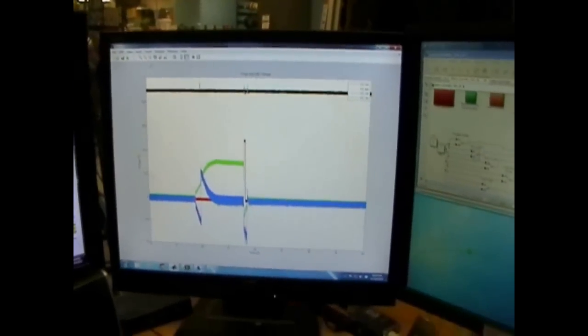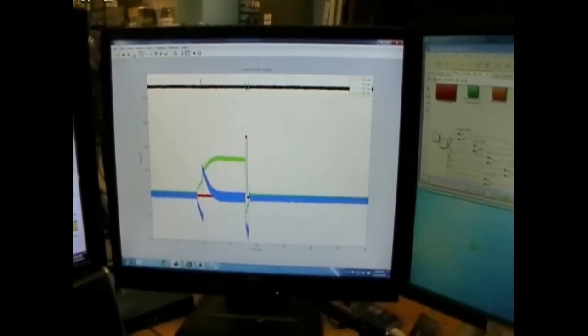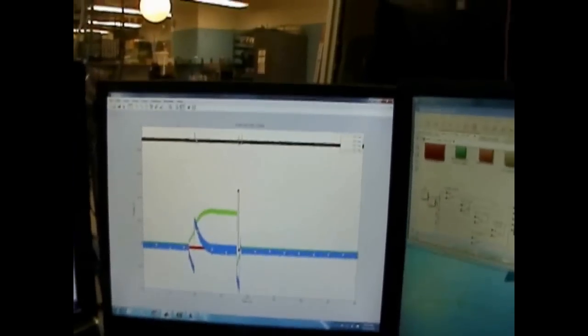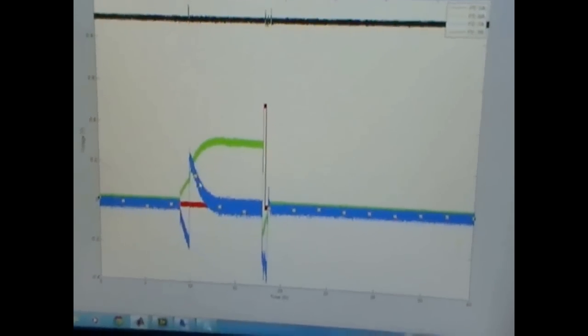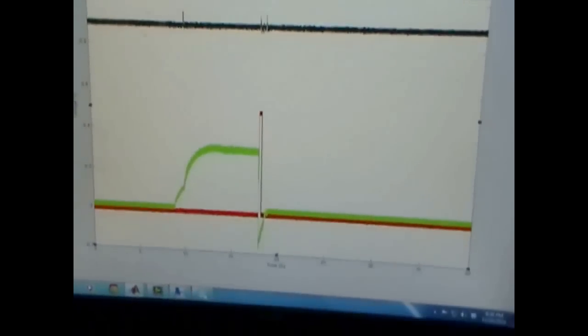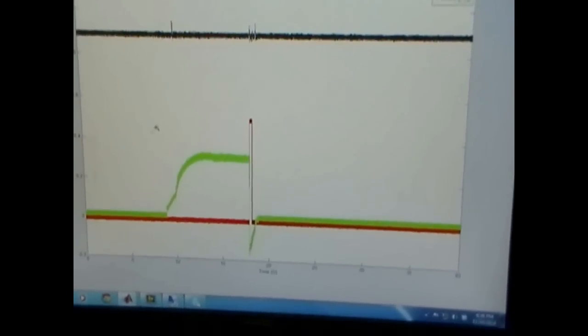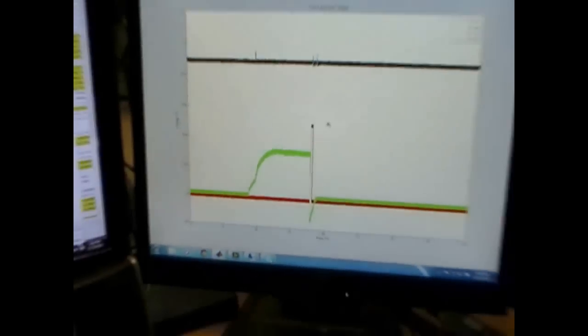This is how the power was drawn. So the black is basically the DC link voltage, which was pretty stable, except at some points here, but it is within the bound expected. And also the green curve shown here is the power which is drawn from the generator. And as you can see, as the speed ramped up, it was also bumpless, and the generator didn't see any bump in the power drawn by the overall drive. So it was bumpless both on the drive side as well as on the generator side.